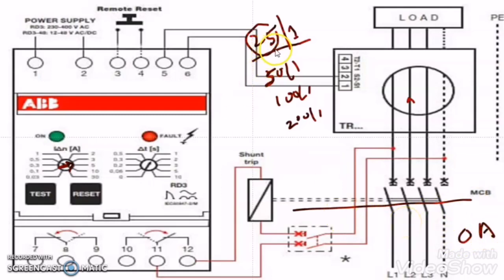Though there is a CBCT, and the CBCT has a range to check the difference till 25 ampere of current, as the ELR is set at 5 ampere, the CBCT will not reach that limit, as the ELR will trip the circuit and the leakage current will become 0. Now let us check another case.